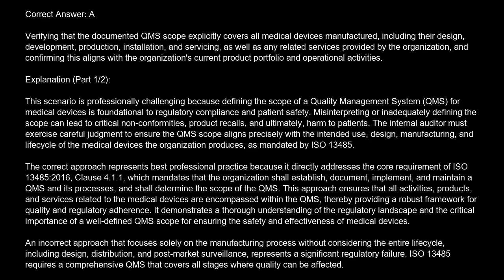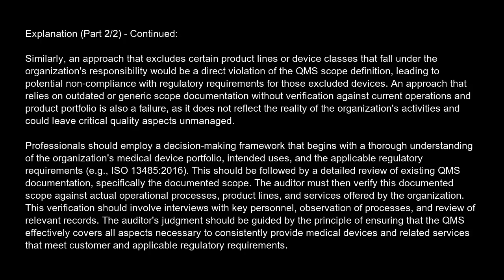An incorrect approach that focuses solely on the manufacturing process without considering the entire life cycle, including design, distribution, and post-market surveillance, represents a significant regulatory failure. ISO 13485 requires a comprehensive QMS that covers all stages where quality can be affected. Similarly, an approach that excludes certain product lines or device classes that fall under the organization's responsibility would be a direct violation of the QMS scope definition, leading to potential noncompliance with regulatory requirements for those excluded devices.